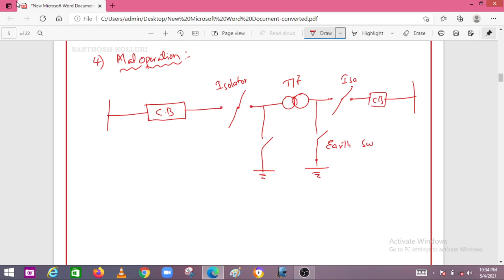The order of opening the transformer here. Whenever there exists a fault, for example, I want to disconnect this transformer from the network. So how to open the transformer? Order of opening the transformer. First you have to open the circuit breaker, because we already discussed this. The function of circuit breaker and isolator is the same: to break the circuit or to make the circuit. But the property of the circuit breaker is to quench the arc existing between the contacts. So that is the main application of the circuit breaker compared to the isolator.